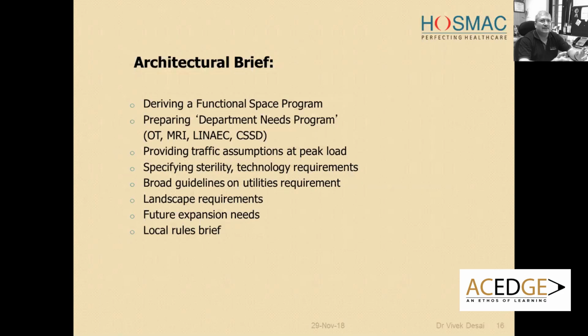Any expansion need you will need to know now, because you cannot size a water tank later. When making provisions for a generator or transformer, you need to understand that a 200 bed facility is going to become 300 beds, and it will need more power, more water—so that space you have to keep today, and if you're going vertical, you'll have to keep foundations accordingly. So future expansion needs will need to be understood.